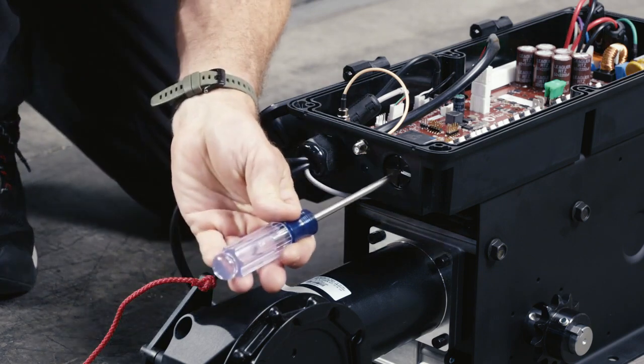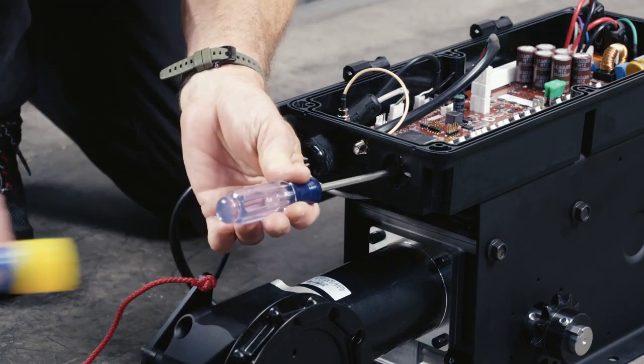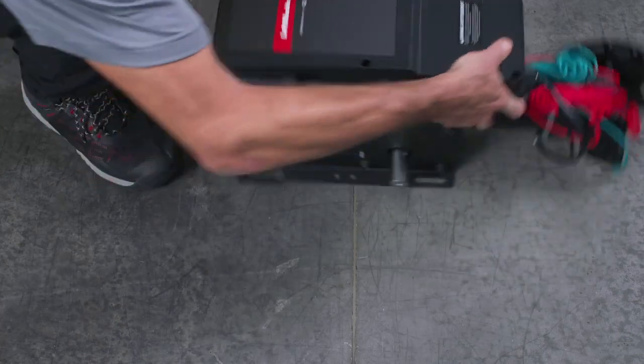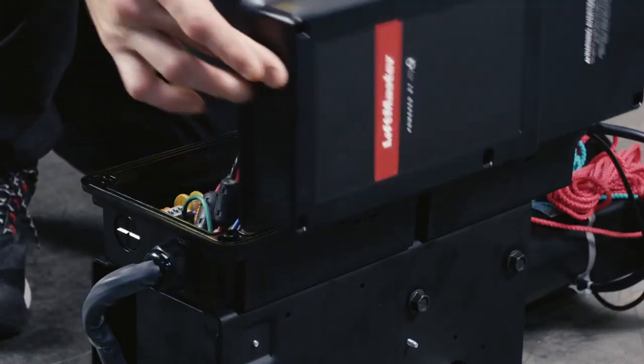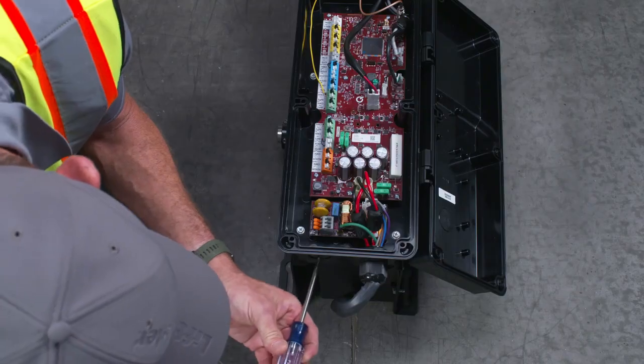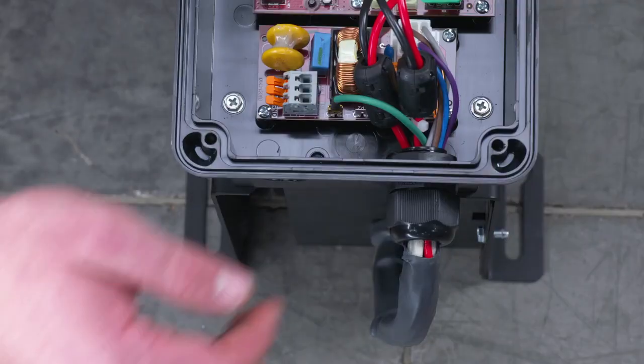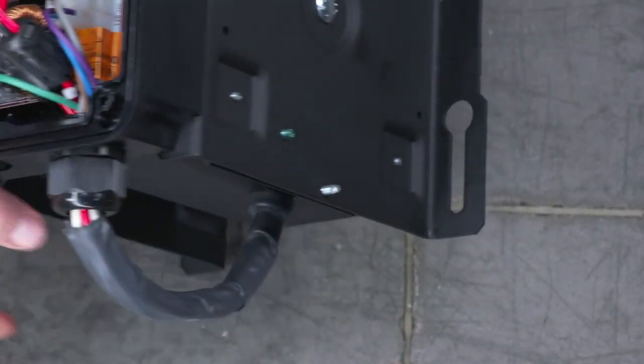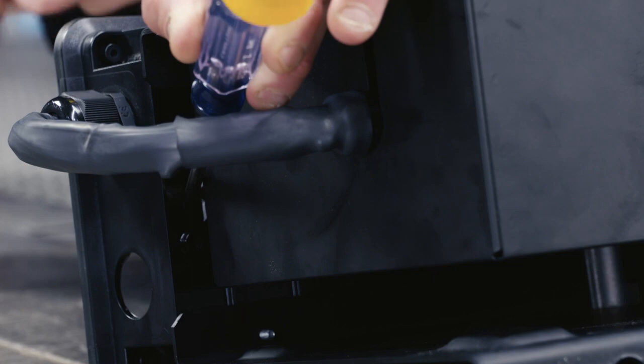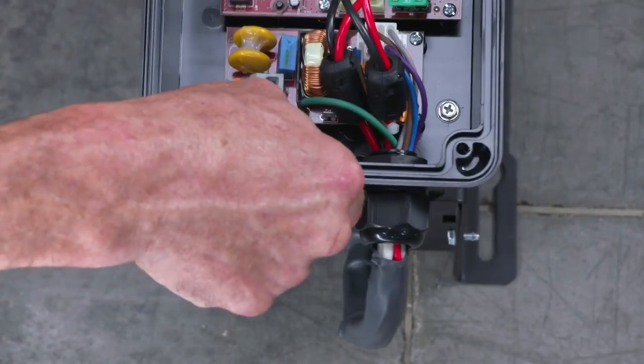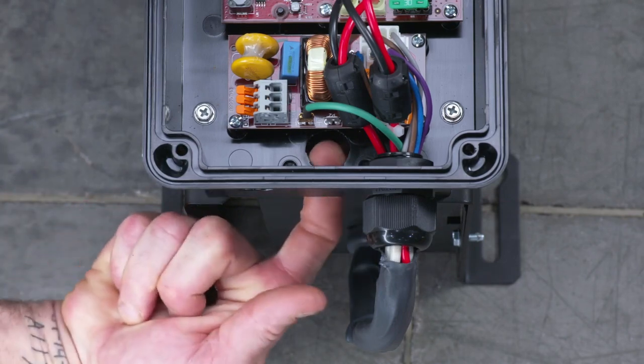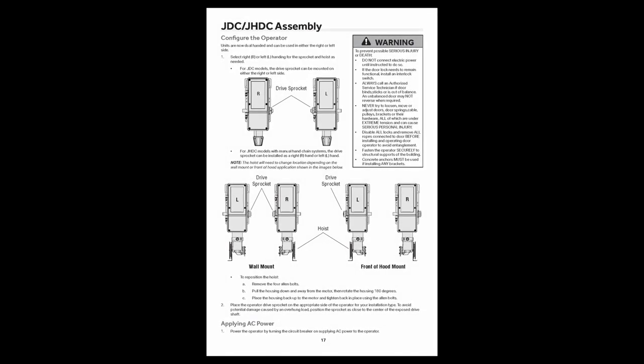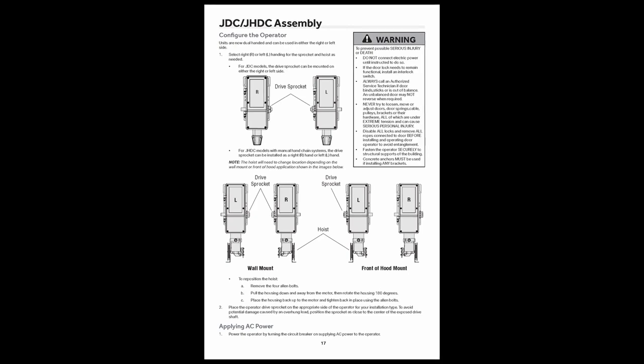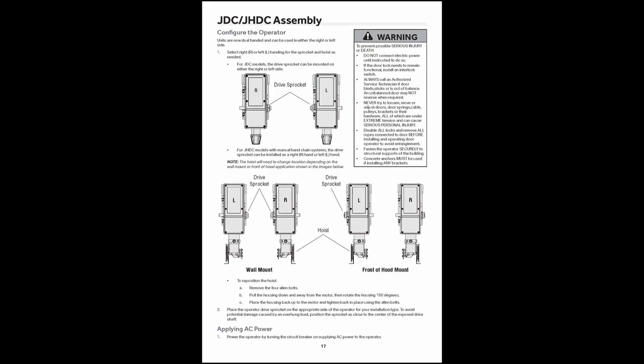It is recommended to remove the knockouts for all the wiring connections, including the battery kit, before mounting the operator. Be careful not to damage the components inside the case. JDC and JHDC are dual-handed, so they can be installed either on the left or right side of the door.